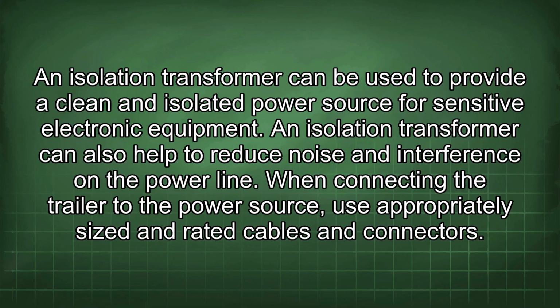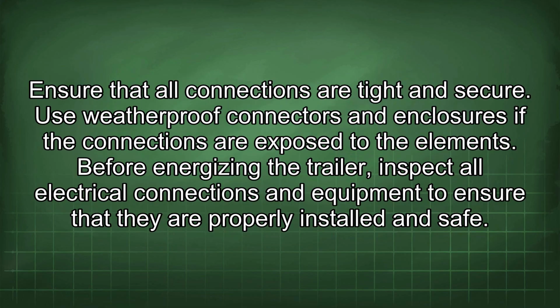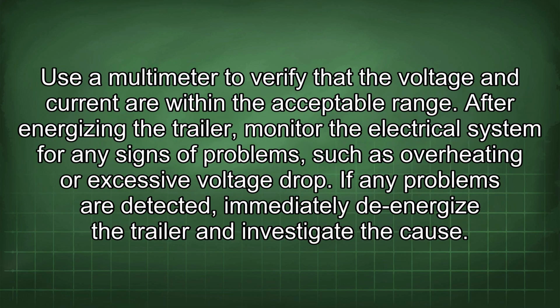When connecting the trailer to the power source, use appropriately sized and rated cables and connectors. Ensure that all connections are tight and secure. Use weatherproof connectors and enclosures if the connections are exposed to the elements. Before energizing the trailer, inspect all electrical connections and equipment to ensure that they are properly installed and safe. Use a multimeter to verify that the voltage and current are within the acceptable range. After energizing the trailer, monitor the electrical system for any signs of problems such as overheating or excessive voltage drop. If any problems are detected, immediately de-energize the trailer and investigate the cause.